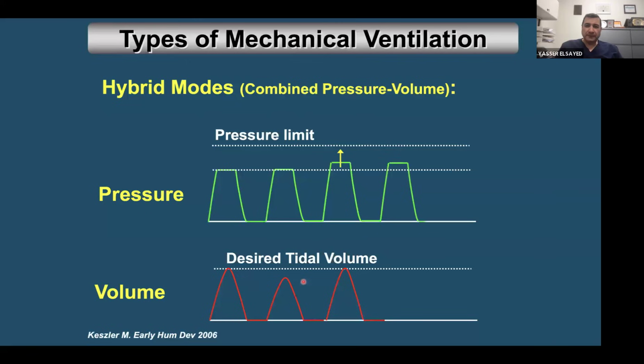What about if the tidal volume in a different breath is exceeding the preset? Now you have higher tidal volume. I don't need that high. So that will synchronize the machine, ask the machine, please deliver less pressure to avoid volutrauma. So the pressure will be back to the 5 ml, which is the preset. So you guys, please set on the machine 5 or 6. So the machine all the time is trying to adjust the pressure up and down to match that preset volume. I hope that makes sense to everyone.